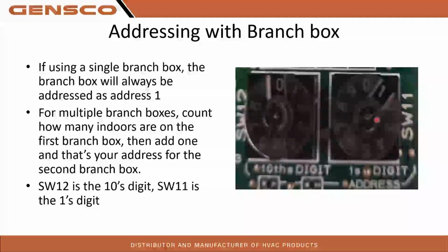Again, for pretty much every single system you do that's just a single branch box, this will always be set to just 1. That way you're telling it address 1 is on this branch box. And because you don't have a second branch box, you don't need to worry about adjusting any other addresses. So that's all you got to do on that branch box there as far as addressing goes. There's some dip switches that you need to set, and I'll get to those here in just a little bit.